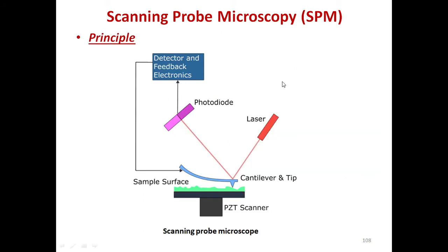Principle. Here is a schematic diagram of an SPM. It is provided with a cantilever and a tip, or a probe, which is coming in contact with the sample surface. The sample is driven by the PZT scanner in X, Y and Z direction. When the laser falls on the tip, it gets deflected, and this deflected light is captured by the photodiode. The detector and the feedback electronics control all these elements.